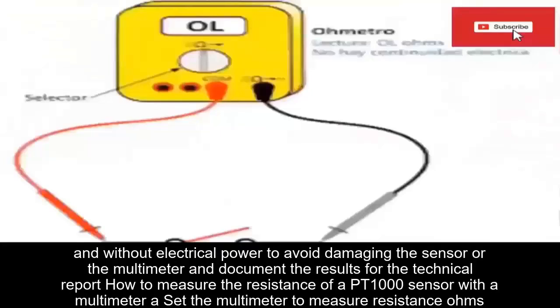If the multimeter indicates continuity, there will be a beep or a reading close to 0 ohms, meaning the circuit is complete. If the multimeter shows OL or infinite, it indicates an open circuit. Ensure the sensor is disconnected and without electrical power to avoid damaging the sensor or the multimeter, and document your results for the technical report.